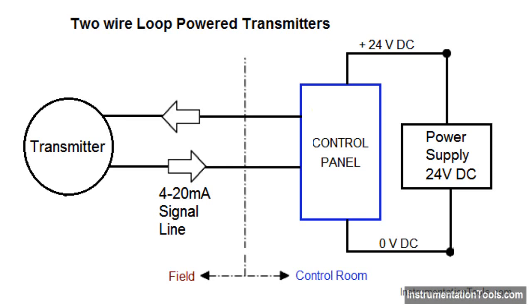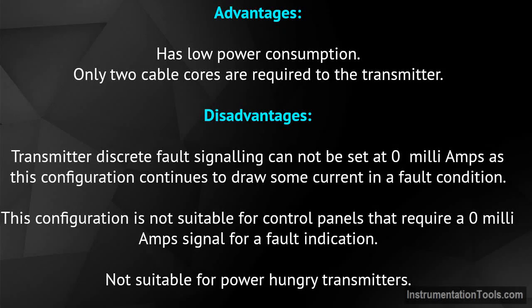Two-wire loop powered transmitters. This configuration supplies power and the 4 to 20 milliamp signal over a two-wire loop connection between the transmitter and the control panel. Not all transmitters can be wired in this format; they must be specifically designed to accommodate this configuration. Advantages: low power consumption, and only two cable cores are required to the transmitter.